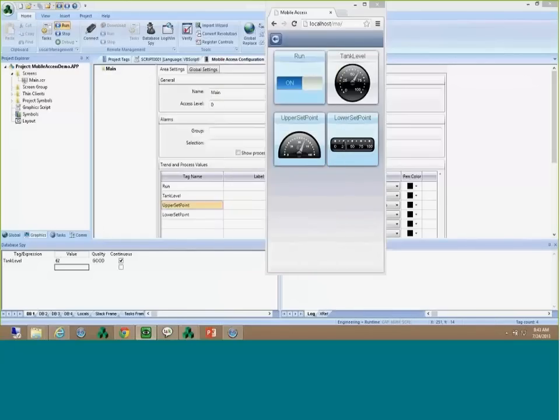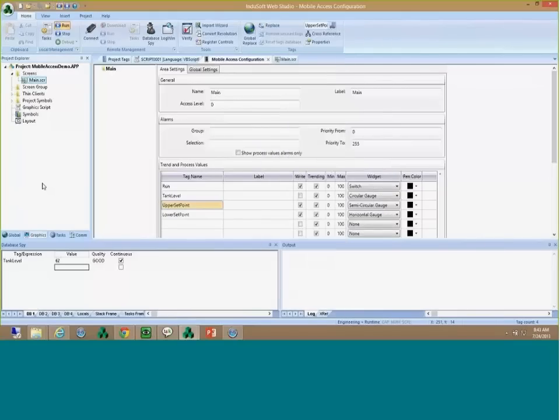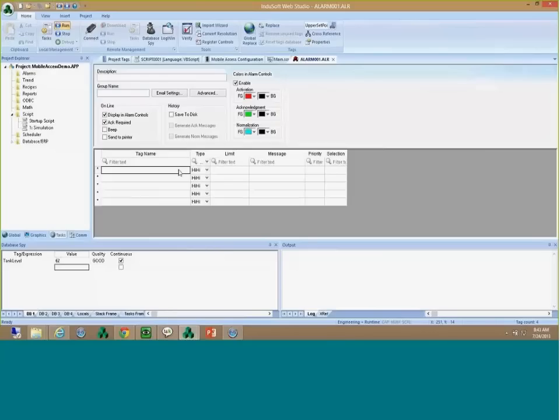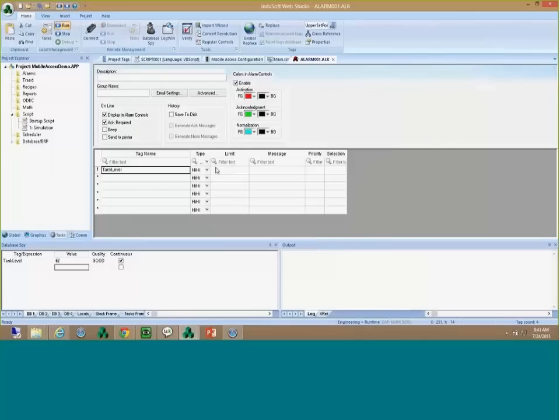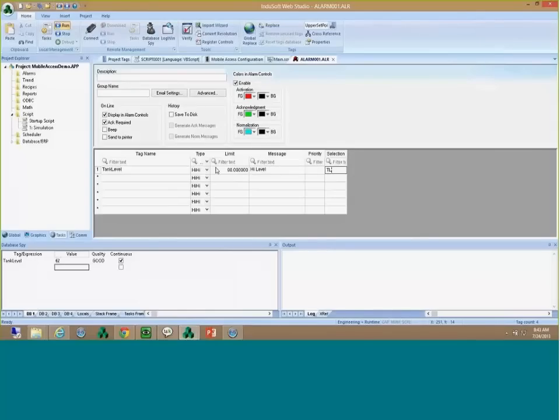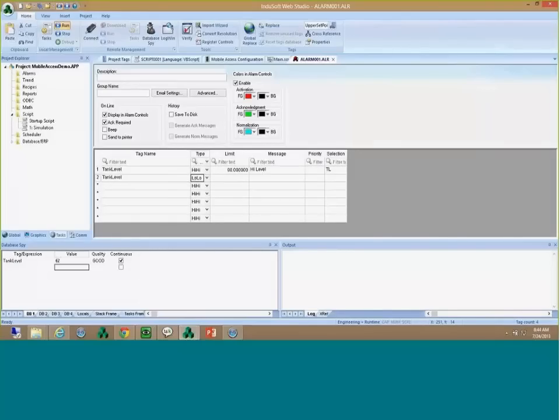Now I want to show the next capability — configuring alarms. I'm going to insert an alarm table and add a few alarms. First, I'll select the 'tank level' tag and set a limit of 80 — if my tank level goes to 80, I'll show a message 'high level'. In the selection field I'll type 'TL'. I'll copy this tag and add a low alarm as well — 'low level' — and also call this 'TL' in the selection field.